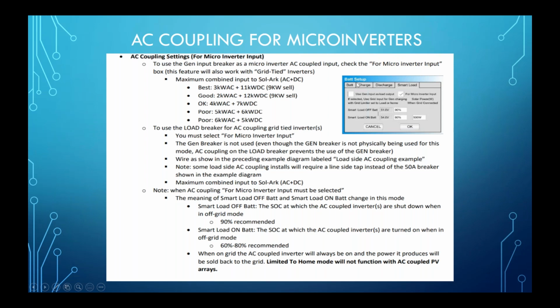This is the menu from our setup. It's in one of the battery setups. The tab is called the Smart Load tab, and right there is a checkbox that says for microinverter input. We've actually changed that now. It says AC coupled input, so this is an AC coupling statement. So if you use the generator input breaker, you want to go to the Smart Load tab of the battery setup, and check right there in the corner where it says AC coupled input.